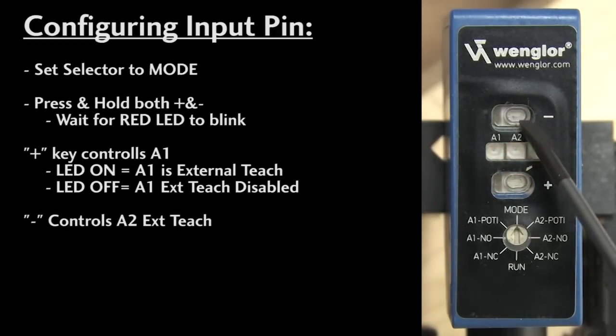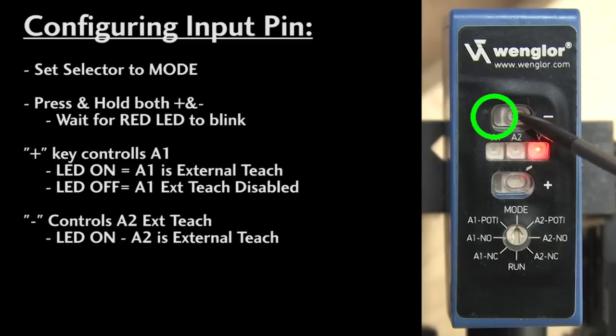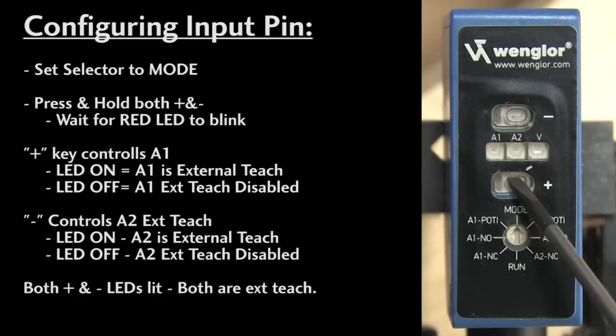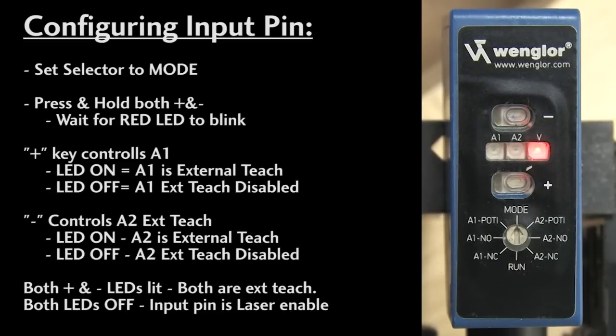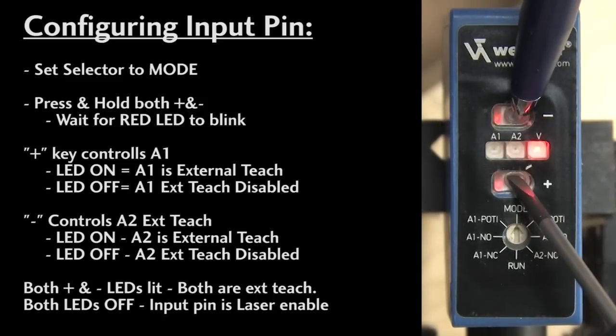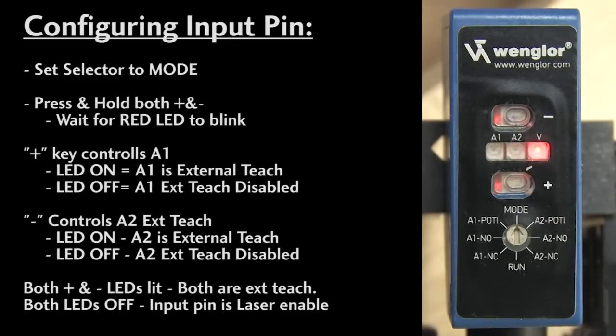Press the minus key to change output A2 to external teach. If the LED is lit, external teach is enabled. If the LED is off, external teach is disabled for pin A2. If both the plus and the minus keys are lit, then the input pin is used to do external teach on both output pins. If both LEDs are off, the input pin defaults to be a laser enable when 24 volts is applied. You can flip that by holding down both keys until they both blink. That inverts the laser enable. The input will now disable the laser when 0 volts is applied.